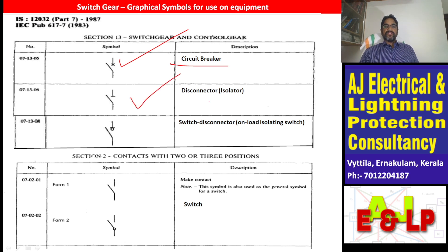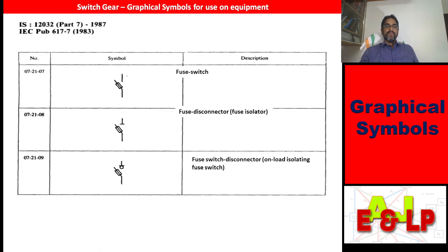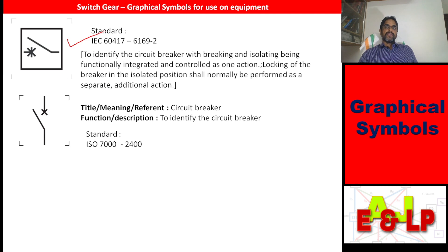This is simply an isolator or disconnector and switch disconnector. Both symbols here mean switch. It is fuse switch and the next one is fuse disconnector — note the difference: it is simply a switch but with one additional horizontal line, so we call it fuse disconnector. Here it is fuse switch disconnector. Now it is circuit breaker with isolation duty — note this reference. Here it is simply a circuit breaker and the reference is ISO 7000.